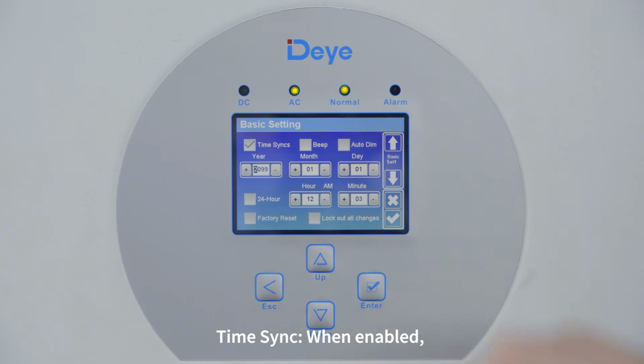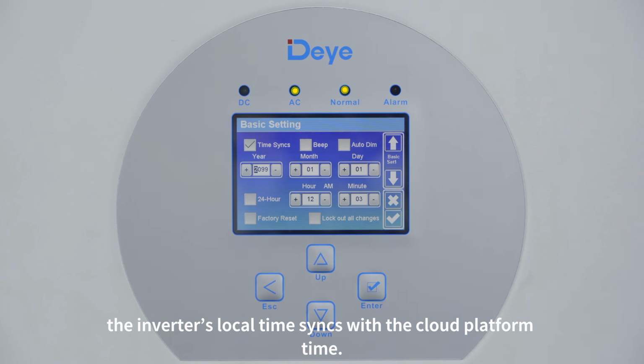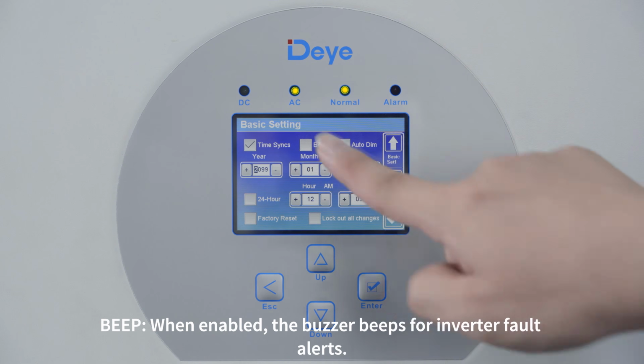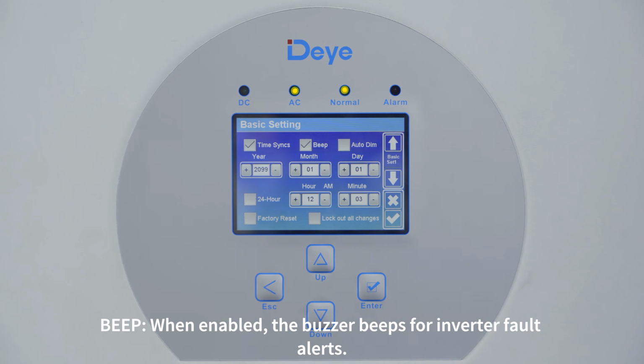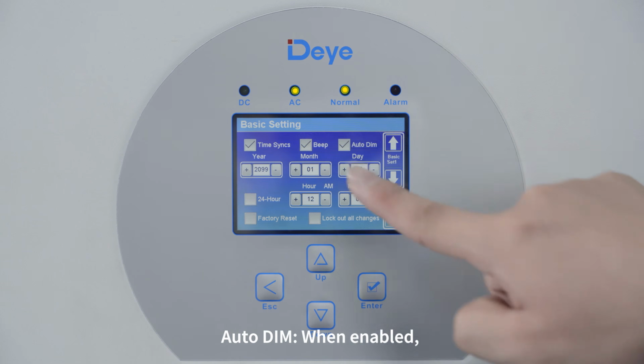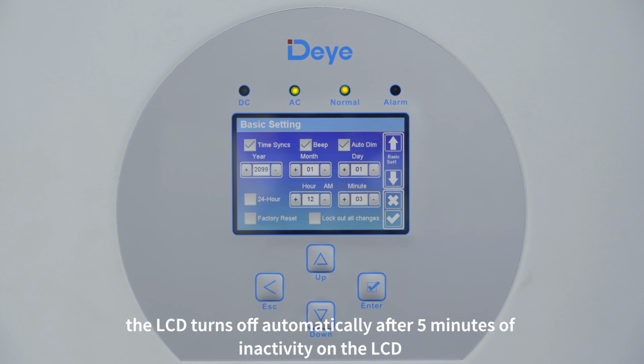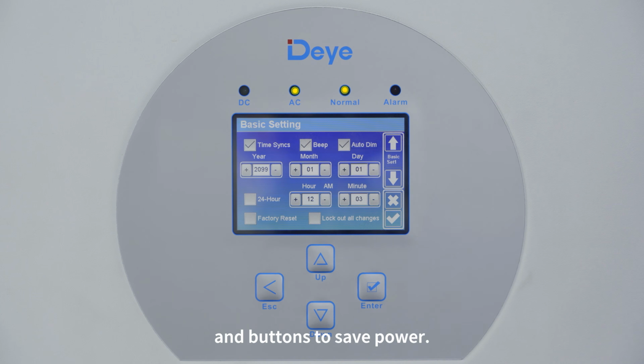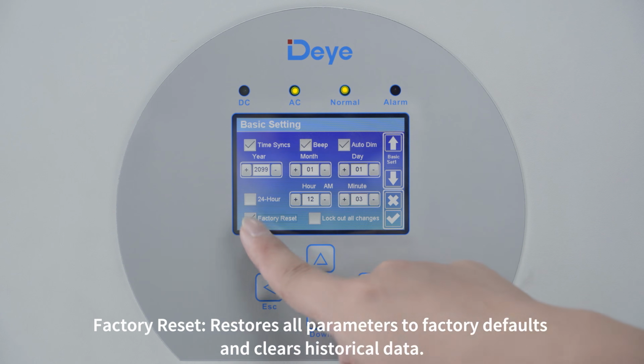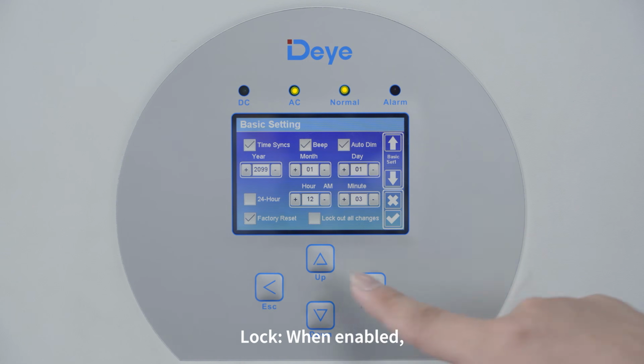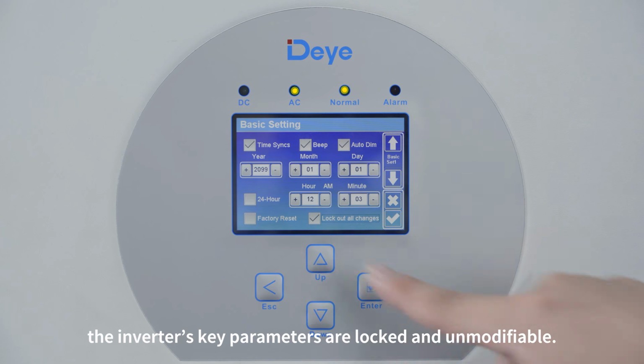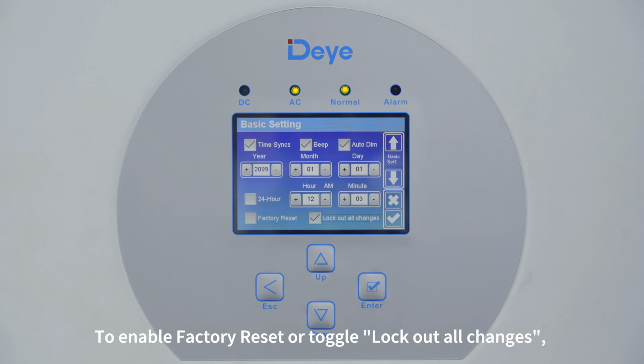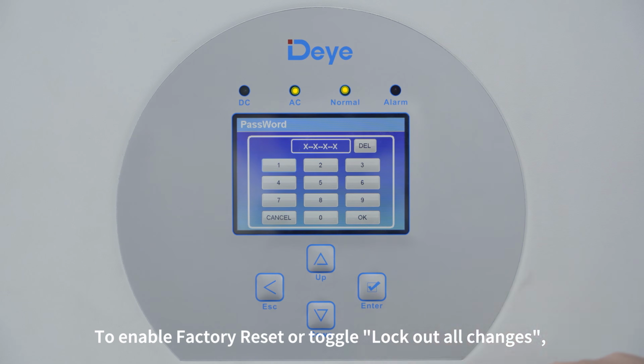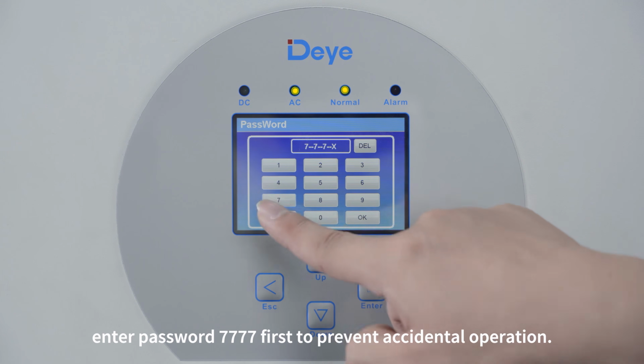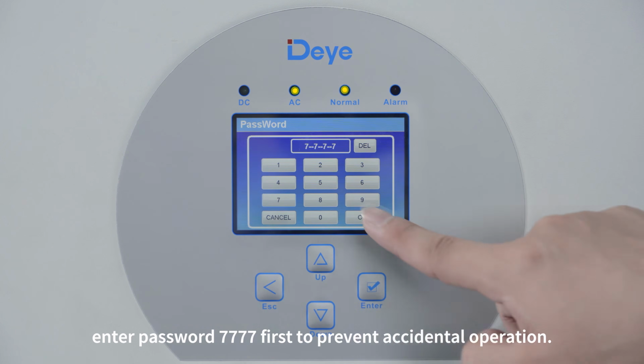Time sync, when enabled, the inverter's local time syncs with the cloud platform time. Beep, when enabled, the buzzer beeps for inverter fault alerts. Auto DIM, when enabled, the LCD turns off automatically after 5 minutes of inactivity on the LCD and buttons to save power. Factory reset restores all parameters to factory defaults and clears historical data. Lock, when enabled, the inverter's key parameters are locked and unmodifiable. To enable factory reset or toggle lock out all changes, enter password 7777 first to prevent accidental operation.